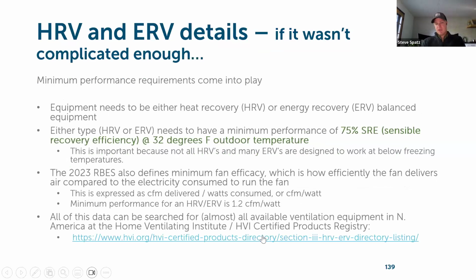So the equipment can be either heat recovery or energy recovery equipment. The difference between the two is that an HRV is only going to be recovering the sensible heat. It's not going to be recovering any of the moisture in the air, any humidity. Energy recovery equipment will be recovering a portion of the humidity in the air that is being extracted on the exhaust side and returning that into the fresh air side of the system to be moved throughout the house. So there's not a requirement for one versus the other.